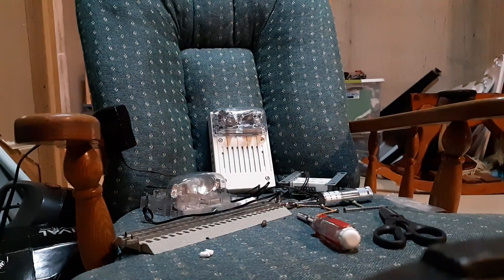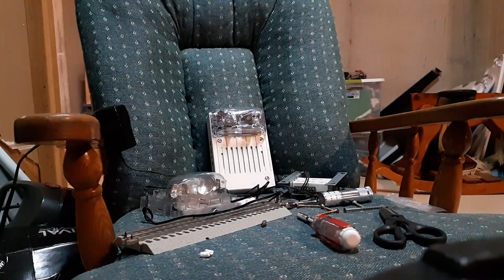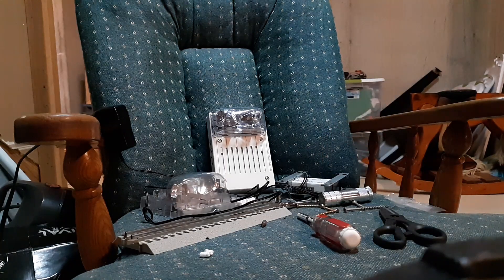I have to figure out one thing though — I do have a bad sync module, because this strobe doesn't flash. I thought I had a bad TrueAlert, but nope, I have a bad sync module. That's great. So I have a bunch of TrueAlert horns and I'll probably use this, but yeah, that's not good. But at least the horn works, so let's do it.